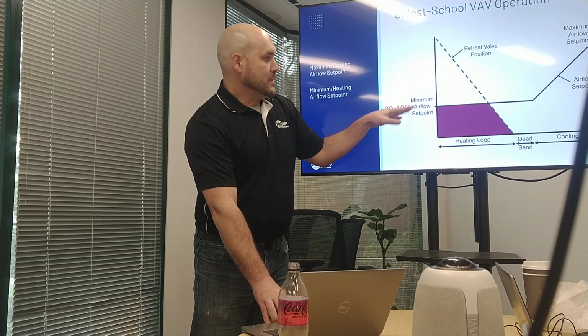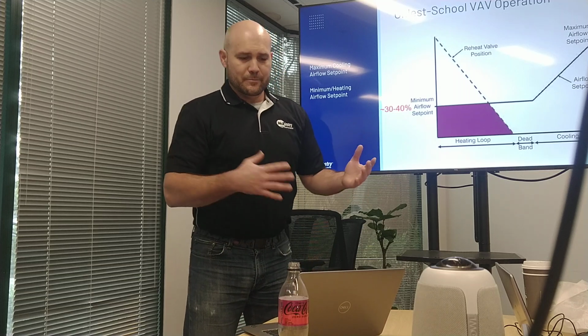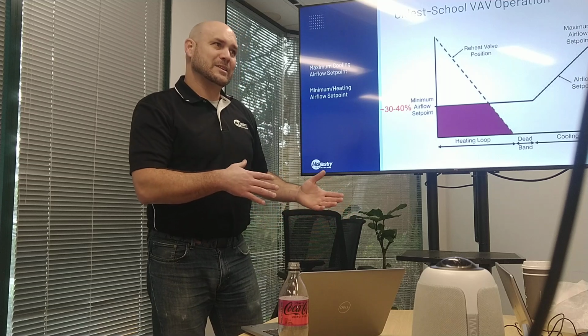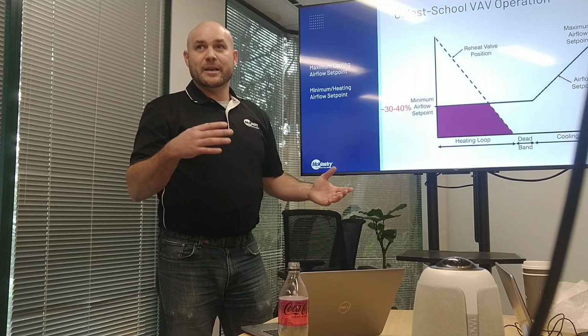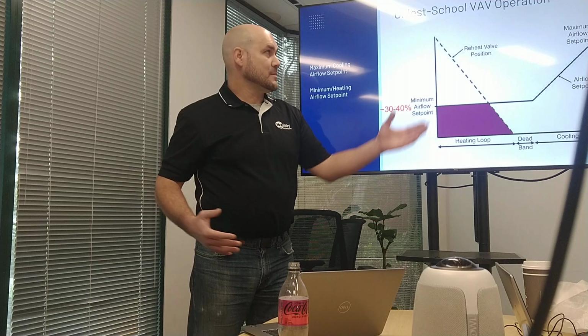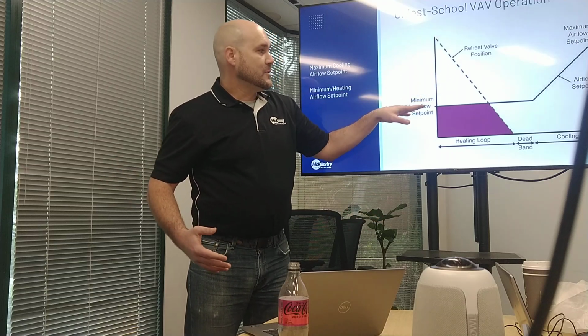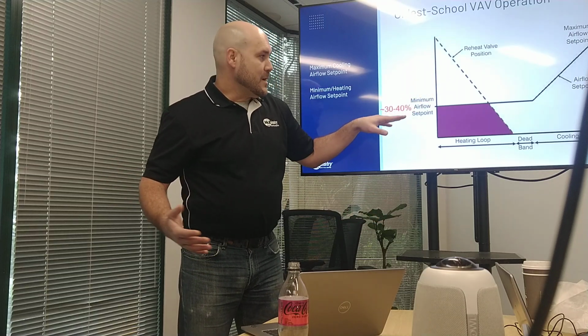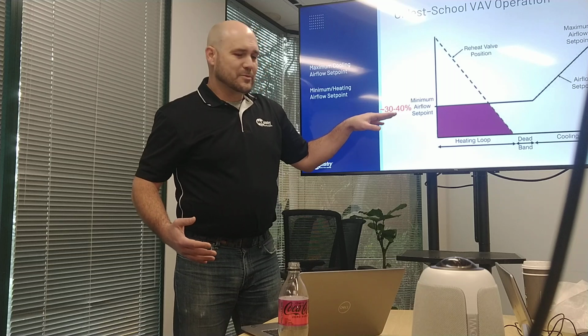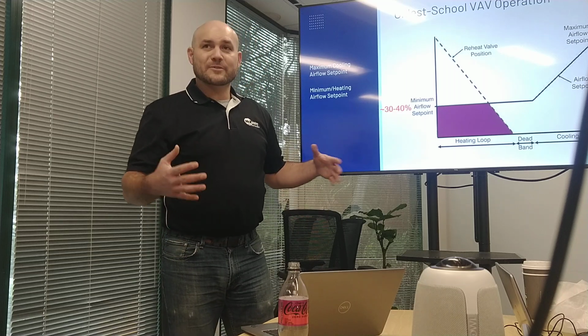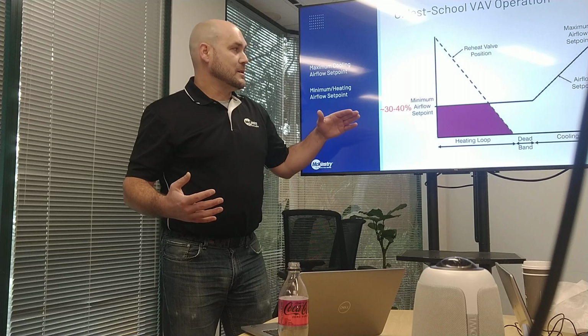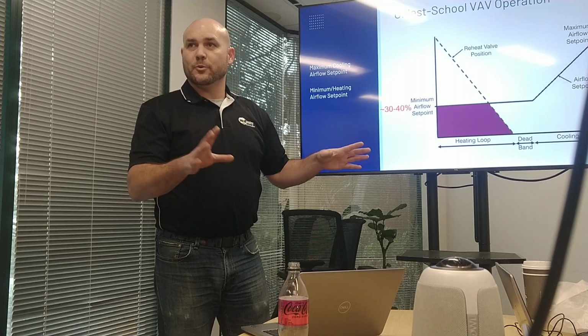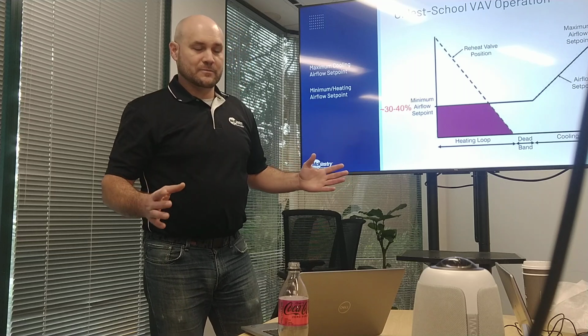And again, this minimum airflow set point tends to be, from my design days, a rule of thumb of 40% of your maximum cooling. If that was 1,000, this would be 400. Maybe 350, possibly as low as 300, but there wasn't a lot of science or thought that went into it. It was just the minimum. You just put 40% in there, and that's the default.